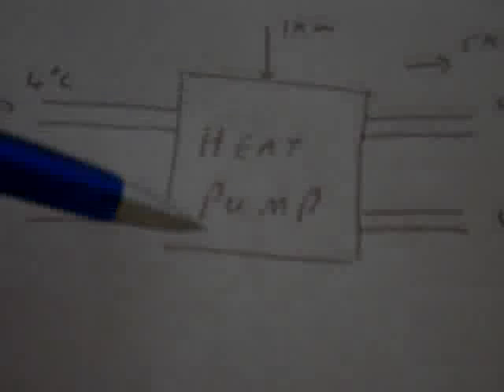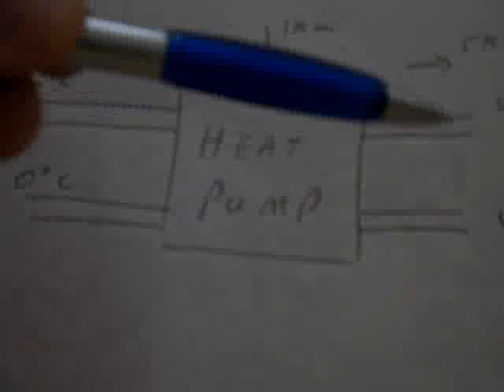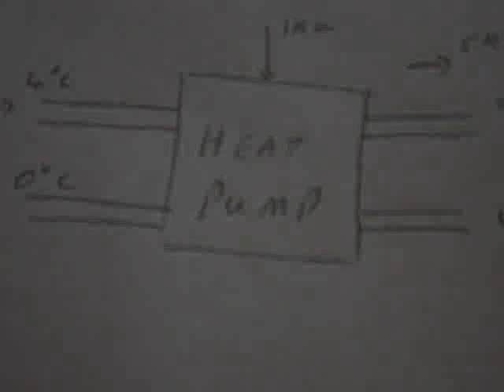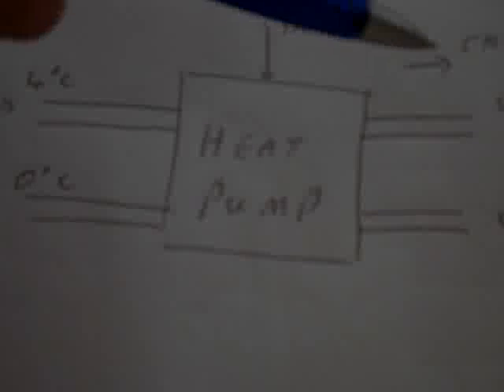The return back into the ground goes back in at about 0 degrees C. The return from the heating system which goes out at 50 comes back at about 40 degrees C. The net result is an overall power gain of between 4 and 5. If we assume it's 5, which is a coefficient of performance of 5, it means for one kilowatt of electrical energy coming in there's 5 kilowatts of heat energy leaving the system.